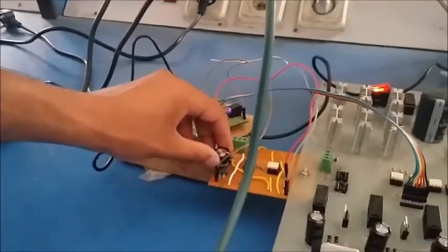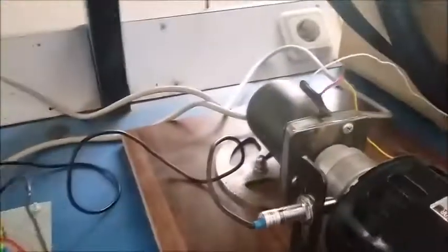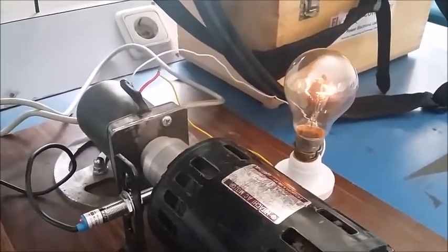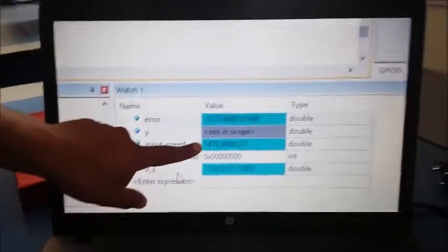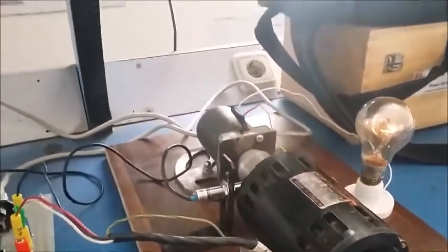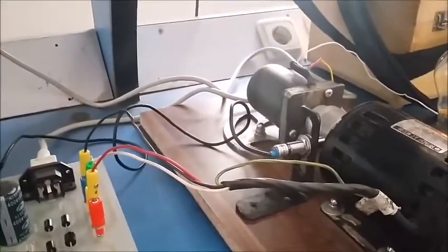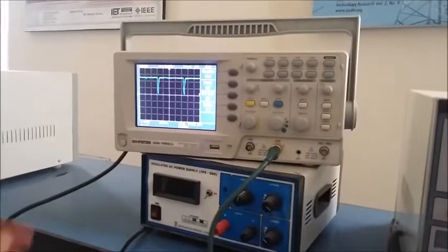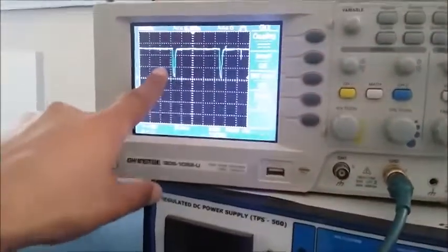I will change the magnitude again using the analog knob. The beauty of this algorithm is that no matter what mechanical load is connected to our induction motor, using the closed loop we can obtain precision and accuracy in speed adjustment. The input speed is very close to the measured speed even with a mechanical load connected — our speed variation is independent of mechanical loading. This is the basic advantage of closed-loop topology in variable frequency drives. The motor is rotating at about 1500 RPM and this is the output pulse of the proximity sensor.